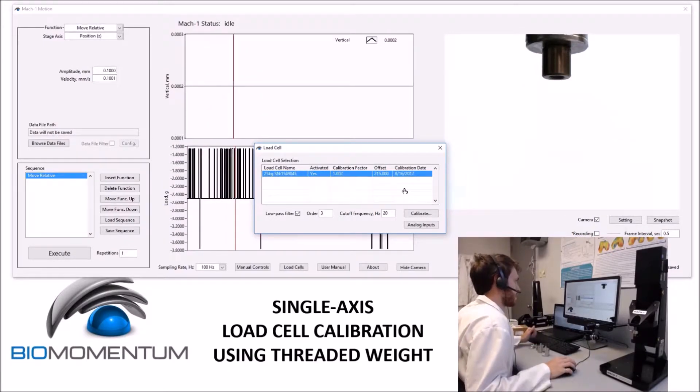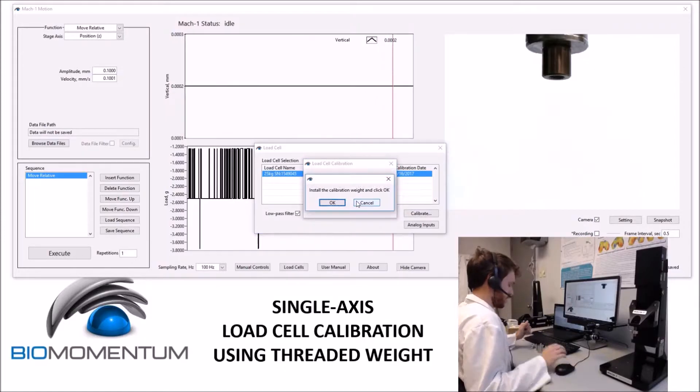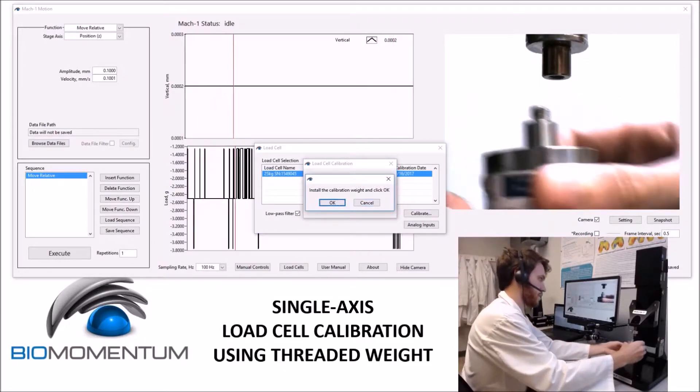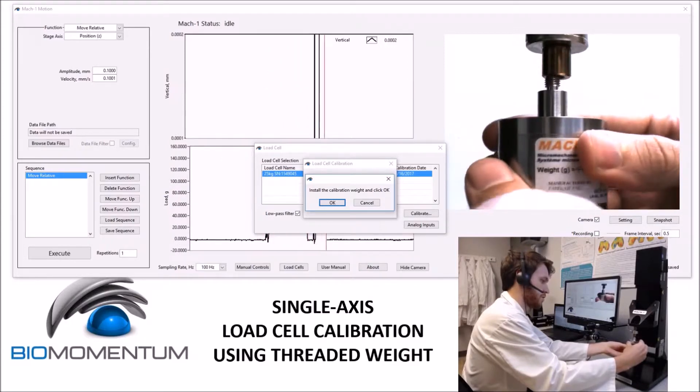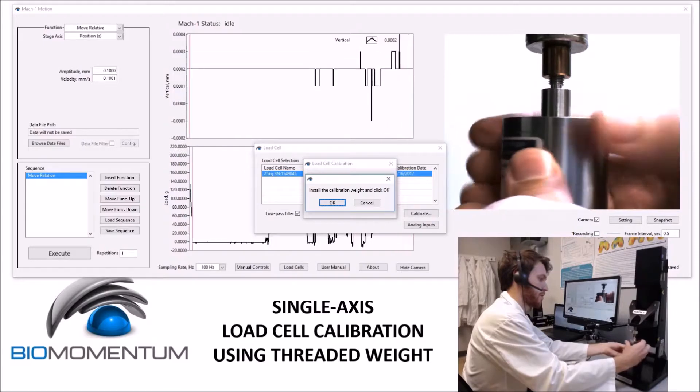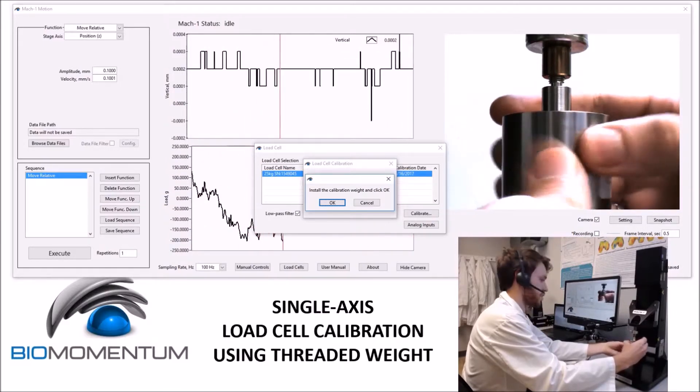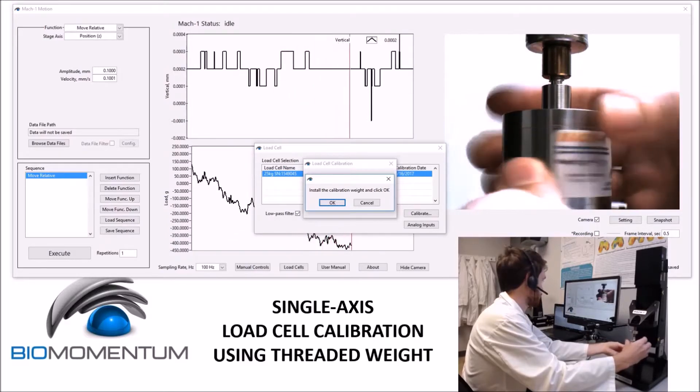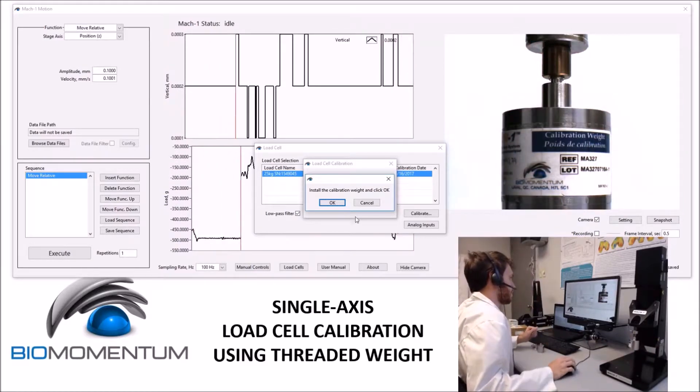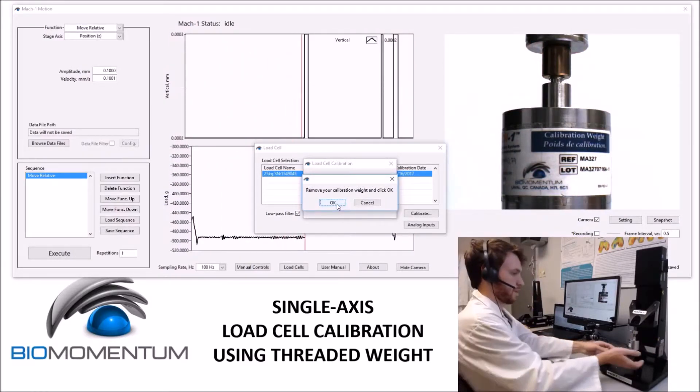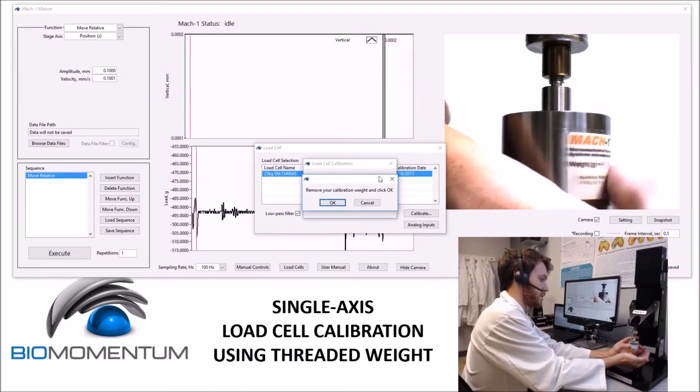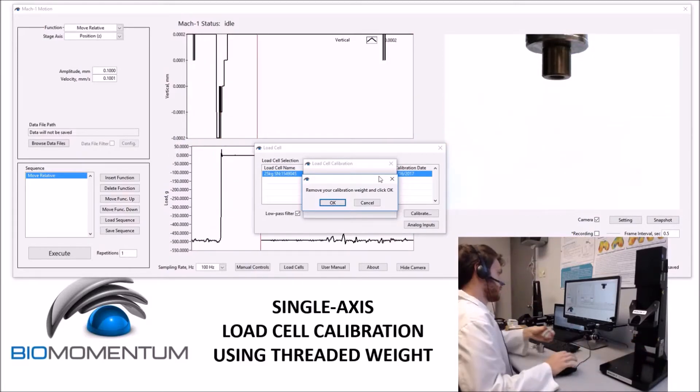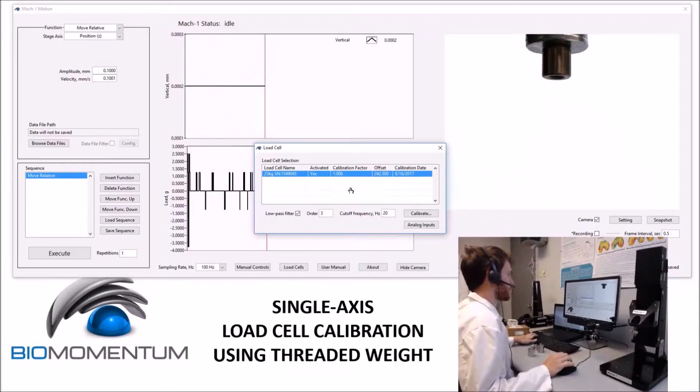The second calibration method is to insert the weight directly into the load cell. For this, I will select the proper calibration weight, click Calibrate, and then follow the instructions on screen. Always be careful when installing anything into the load cell. Sometimes it's prudent to keep an eye on the load cell window, to see how much force you are putting on the load cell currently. To remove the calibration weight, I usually keep one hand at a distance from the weight, and then let it drop into that hand. The load cell is now calibrated.